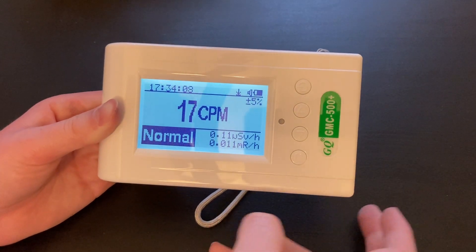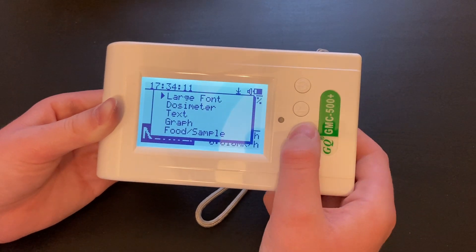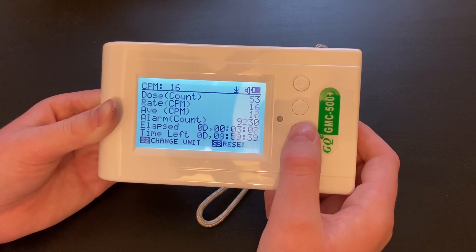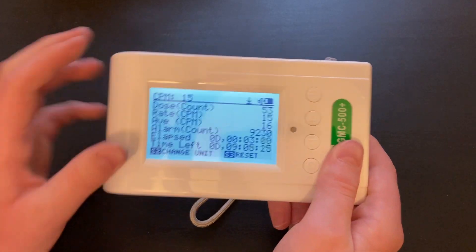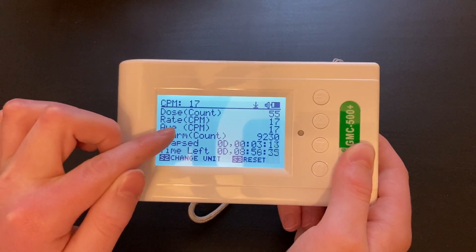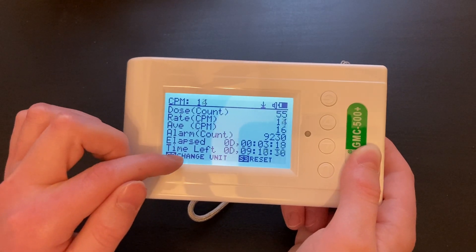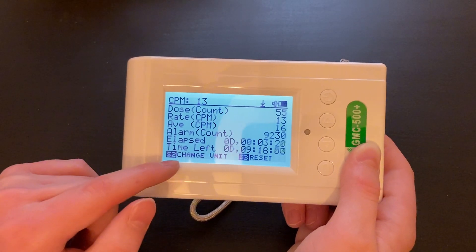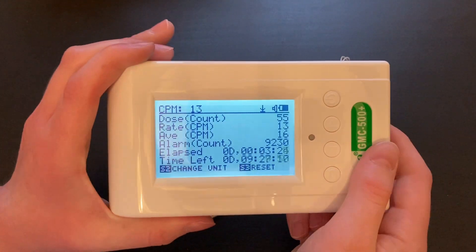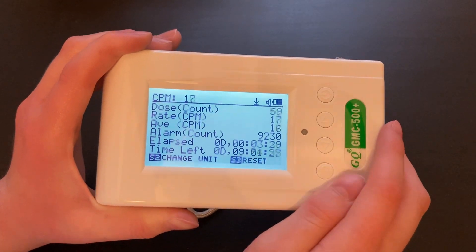There are multiple different modes on this unit, and to switch between them you will click the bottom button. You can use up and down arrows to switch between modes. On the large font mode there's the regular screen. On the dosimeter mode there is a dose display, which is in count for some reason, the rate display for count rate, average, alarm, time elapsed, time left, and there's also a way to change the unit and reset the display. You will notice this is also a timed count status. You can use the scalar function right here.